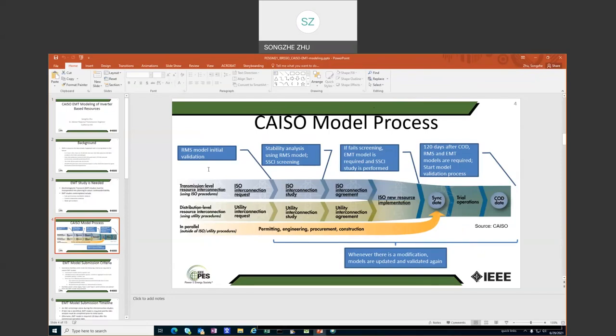Here you see our interconnection process. The major steps are the interconnection request, then the interconnection studies, then executing the interconnection agreement, then the resources go into the new resource implementation phase, and then synchronization and commercial operation. During the interconnection request phase, we only require the RMS model, and we perform an initial validation to make sure the RMS model is good enough for the study and meets all the interconnection requirements and applicable reliability standards. Then during the interconnection study process, we perform stability analysis using the RMS model. Toward the end of the study process, we do an SSCI screening.